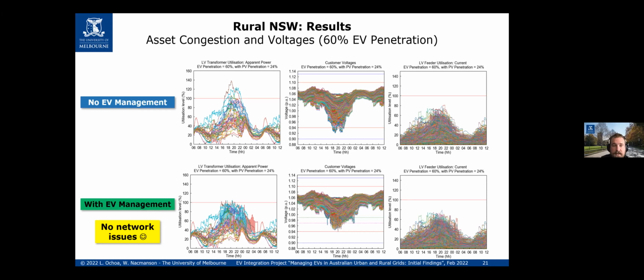The main takeaway is that without management, we have problems with the transformer loading too high and voltage drop issues. When we have EV management and shift demand to times with more capacity, we're able to manage the LV transformer utilization, manage customer voltages, and the LV feeder utilization still has no issues. So with EV management, we solve those issues.